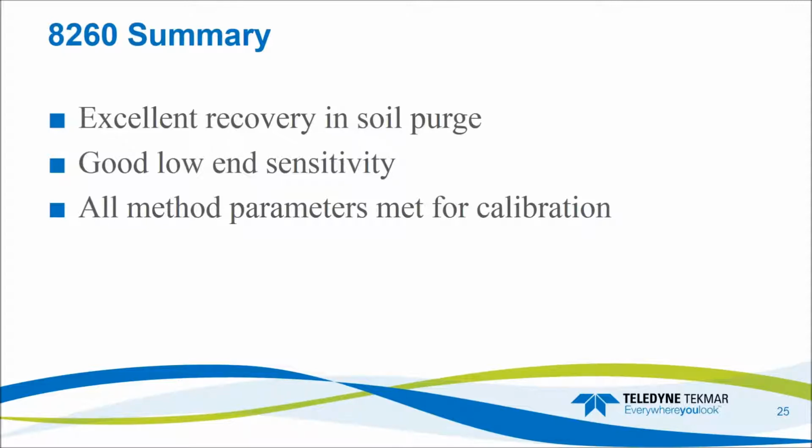We have good low-end sensitivity. We have low MDLs on all compounds, and we met all the method parameters for the calibration. So we did not struggle in meeting calibration requirements, in meeting MDL requirements, those sorts of things. All of those method parameters were met easily because, again, we did not mess with the GC. We were still using helium as a carrier gas.